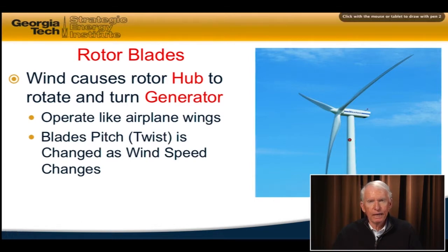That's to maintain the maximum efficiency and to be able to extract the most energy from the wind, since the ideal pitch varies with the wind speed in order to make the rotor's extraction of the kinetic energy from the wind work at its optimum rate. So it's a very sophisticated technology, and it's all automated. It senses the wind speed and decides what pitch it needs and what RPM it needs to be rotating at, and varies it in order to stay on that optimum.